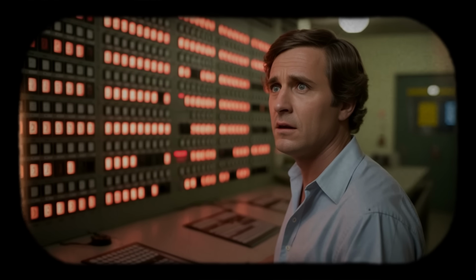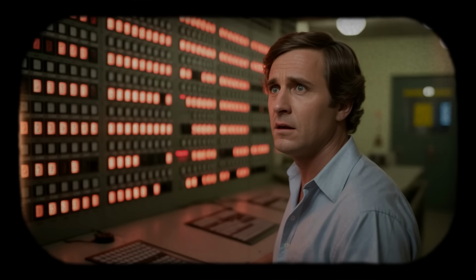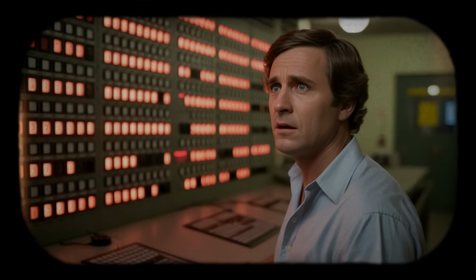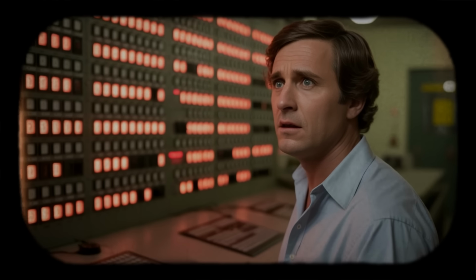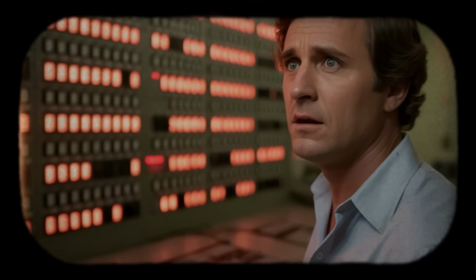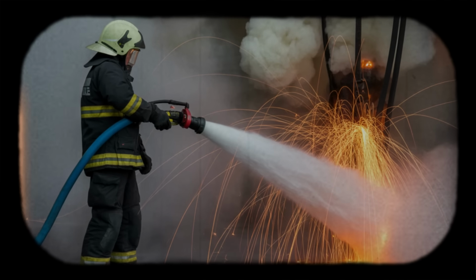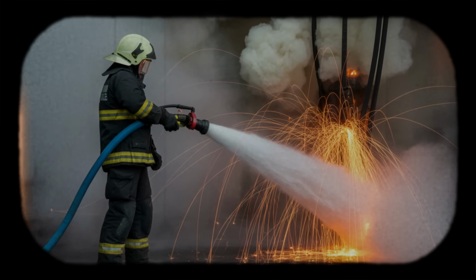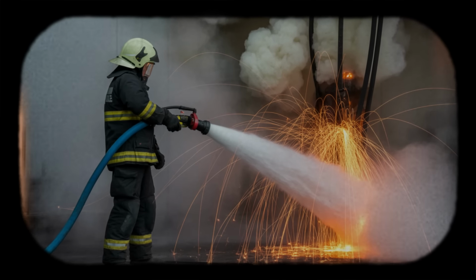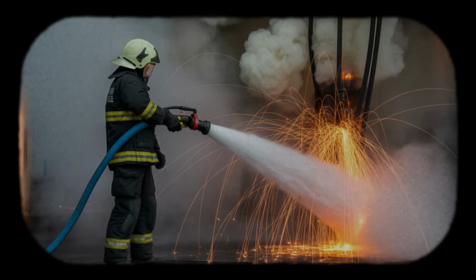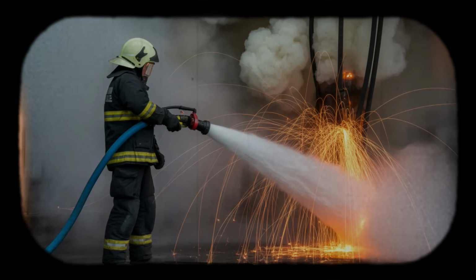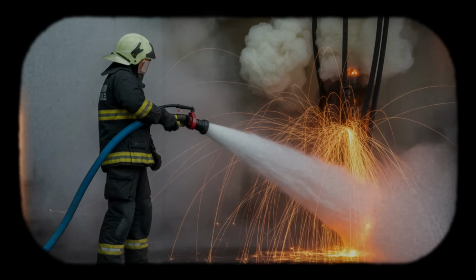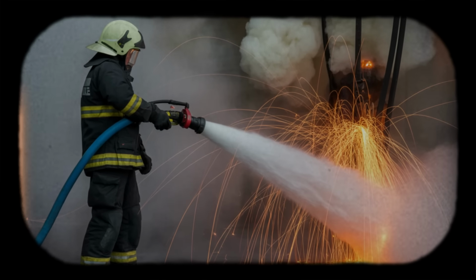12:38 to 12:44 in the afternoon. Cable spreading room. Smoke begins collecting at the ceiling. The air grows hazy. One of the electricians notices the glow inside penetration 5 has intensified. What appeared extinguished minutes earlier is now clearly active again. The fire has spread deeper into the wall cavity where foam and cable insulation provide continuous fuel. The electricians expected a small surface fire, something containable with a portable extinguisher. Instead, the fire is spreading internally along pathways they cannot directly access.